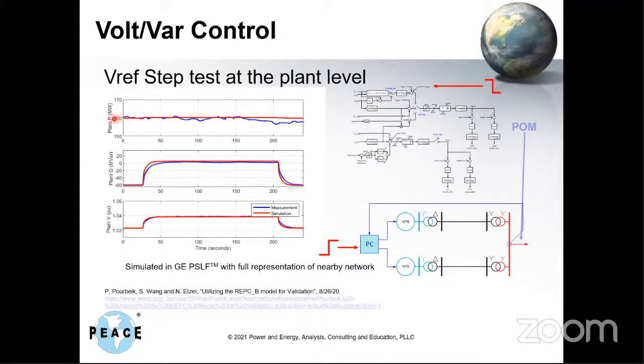This is actual megawatts coming out of the plant. As wind speed changes, the real power changes, but in our simulation we assume constant wind speed, so nothing changes. Here's the reactive power coming out of the plant, and here's the voltage, and you can see the blue stepped, and the simulation also matches quite nicely. In this case, the model is one of these standard models, what we call second generation generic models.